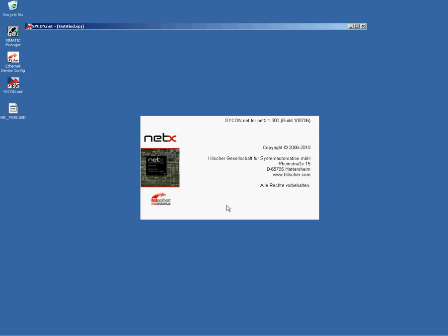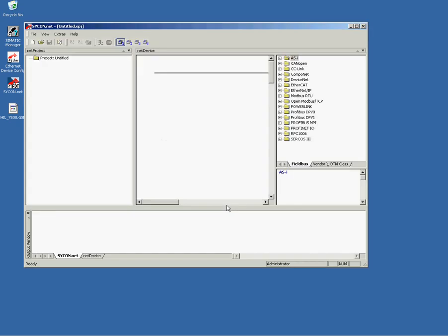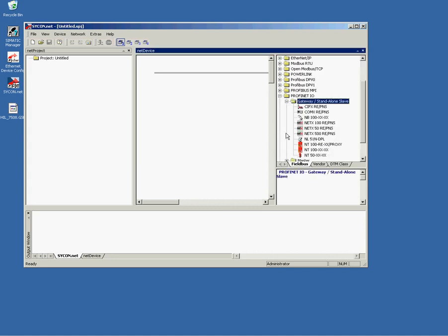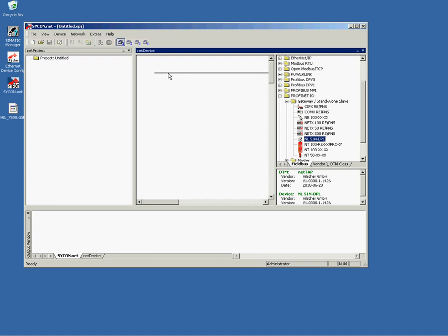As next, we have to start Sycon.net configuration utility. This utility comes up with an empty bus line, where we usually connect our Hilscher devices to. To the right hand side, you find the device catalog from where you drag and drop your devices of your choice. You find the Netlink proxy device under Profinet and name NL 51N-DPL. Drag and drop the device to this gray bus line with your mouse.